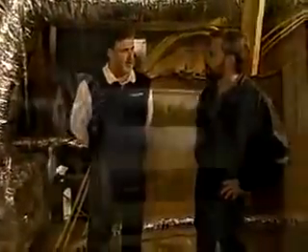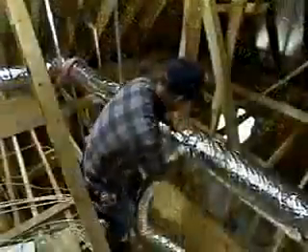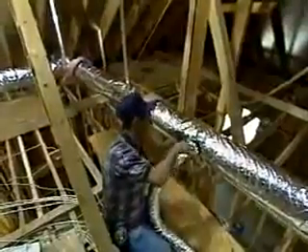Steve, tell me how the unit goes together. Our units are modular, which means the blower section is separate from the heating section, which is separate from the evaporator coil. They have shiplap fittings at the bottom so they connect together, and at the top it's completely gasketed with suitcase latches — you latch it and it's airtight. Really easy to install. Up in the attic we've got one main trunk line running around the house with feeder lines — the two inch tubes going to the termination points. They don't have to transition down to different sized ducts; they run one main trunk line and take the two inch tubes off of that.